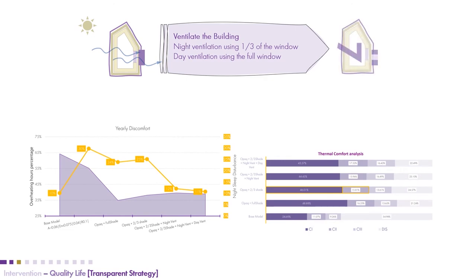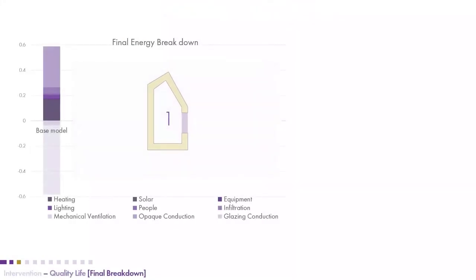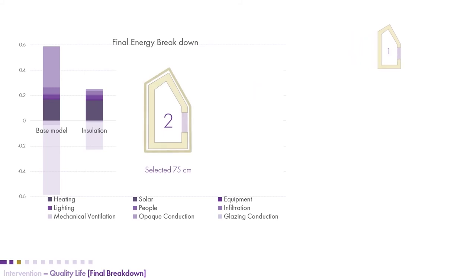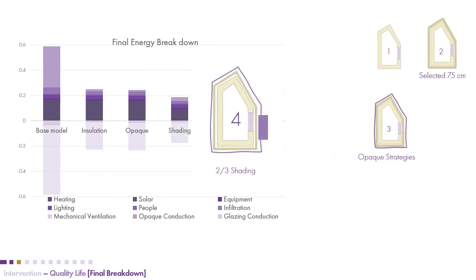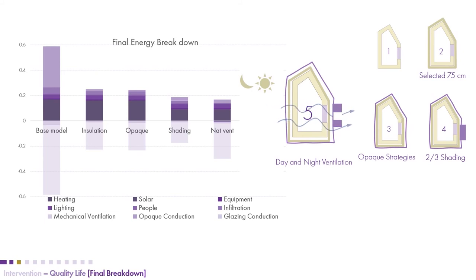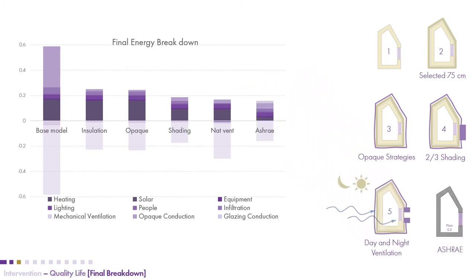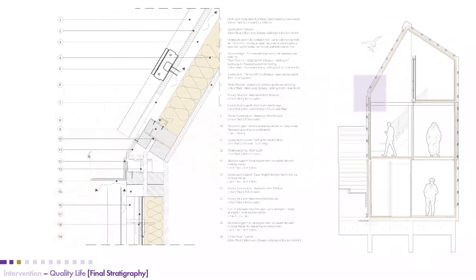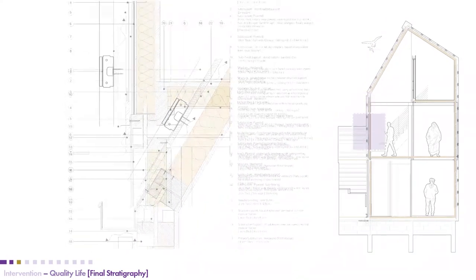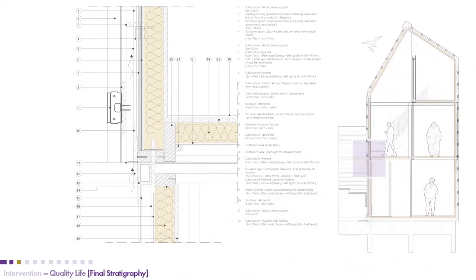The final energy breakdown shows the sequence of improvements: first, insulating the building reduced heat gains through the opaque facade; second, extra opaque adjustments; third, shading reduced gains through the windows; and finally, natural ventilation was added. We can see how close we have gotten to the ASHRAE standard that was recommended from the beginning. These simulations and analyses helped us finalize the construction layers of the different parts of the building.